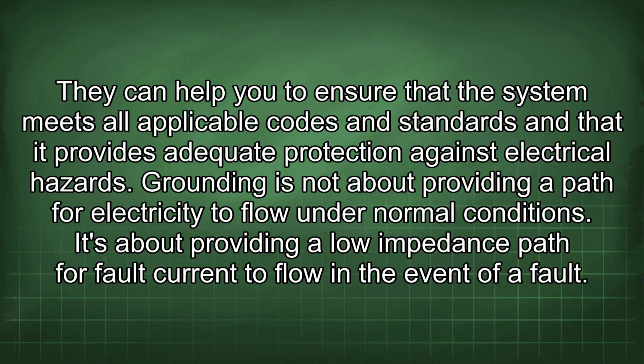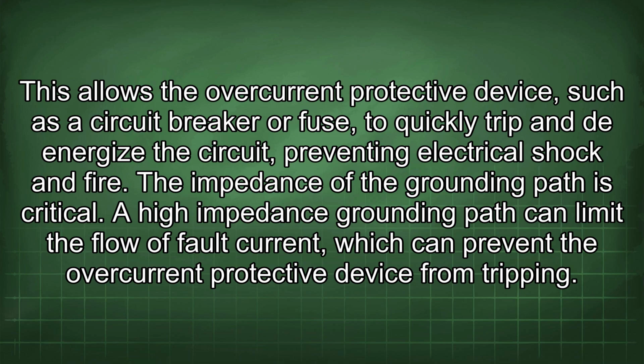They can help you to ensure that the system meets all applicable codes and standards and that it provides adequate protection against electrical hazards. Grounding is not about providing a path for electricity to flow under normal conditions. It's about providing a low impedance path for fault current to flow in the event of a fault. This allows the overcurrent protective device, such as a circuit breaker or fuse, to quickly trip and de-energize the circuit, preventing electrical shock and fire.